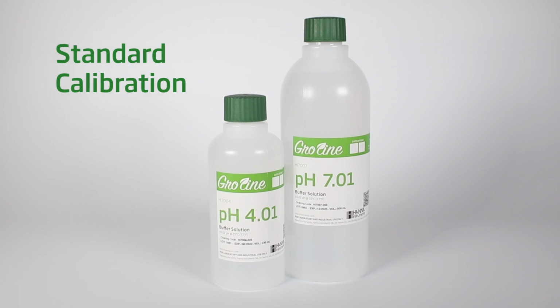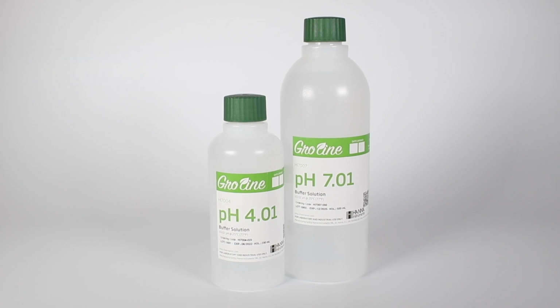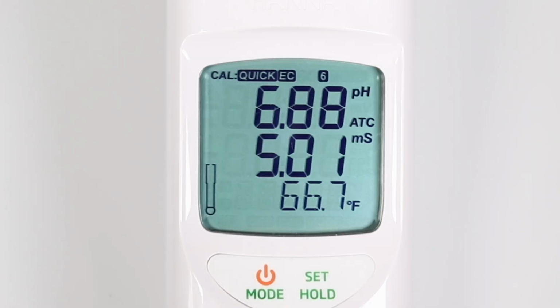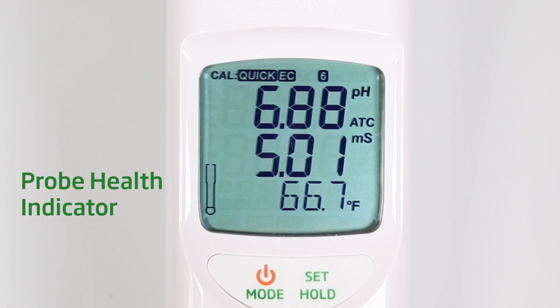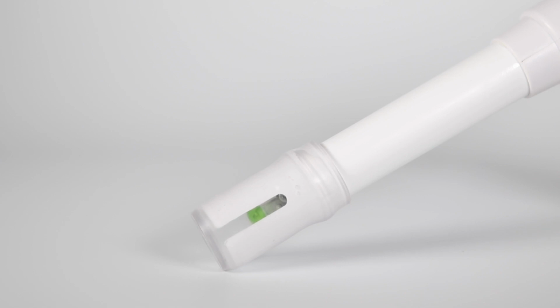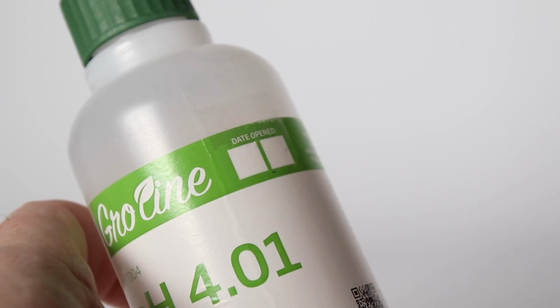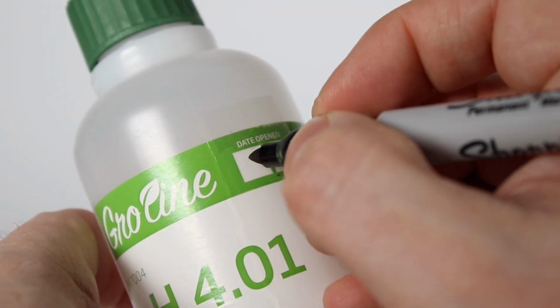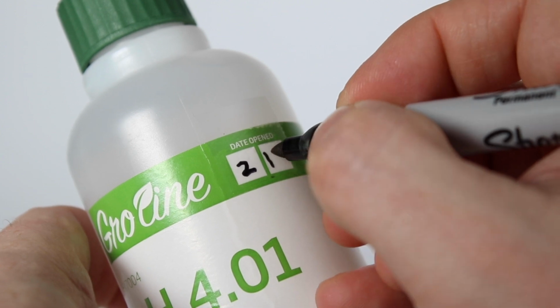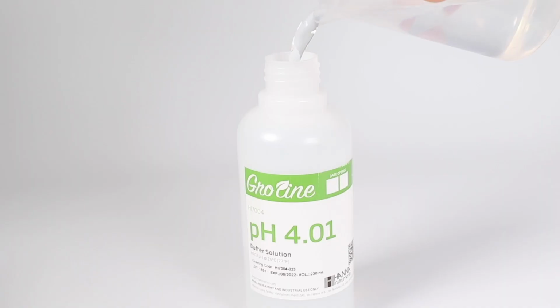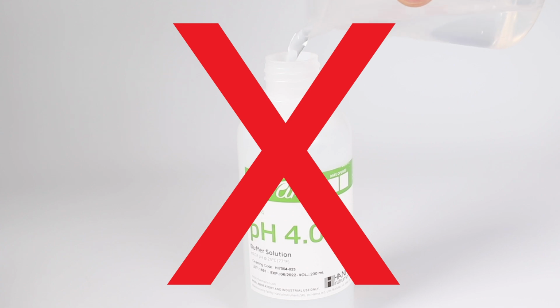Okay, let's perform a 2-point calibration in standard calibration mode. You may use any brand of pH 4 and pH 7 calibration solution for standard calibration. It also allows for the meter to display probe health. Note, the probe health is not displayed in real time. It only represents the health of the probe at the time of calibration. Before you begin, make sure your sensing glass has been hydrated in storage solution for at least 1 hour and has been rinsed for 10 seconds prior to attempting a calibration. Make sure your solutions are fresh. When opening a bottle for the first time, write today's date on it so you don't use it after it has been opened longer than 6 months. Do not pour the used calibration solution back into the bottle.